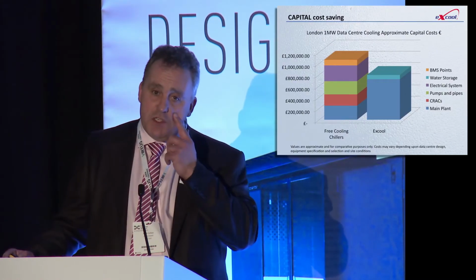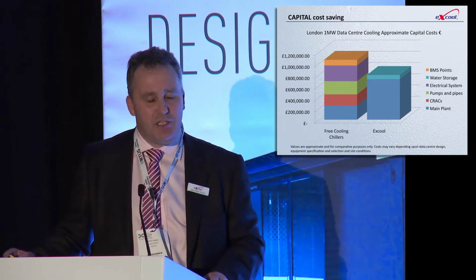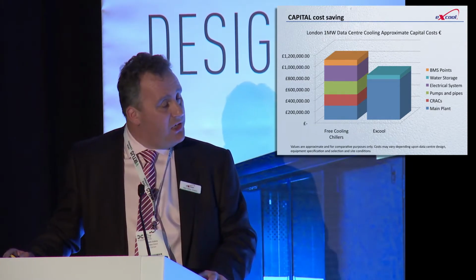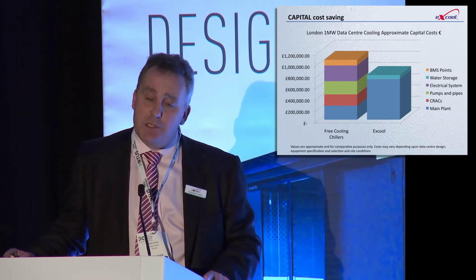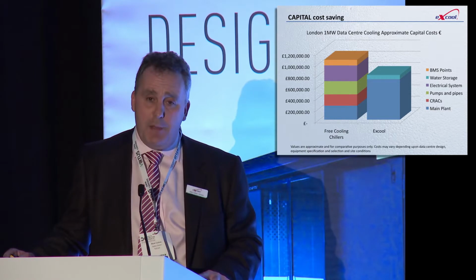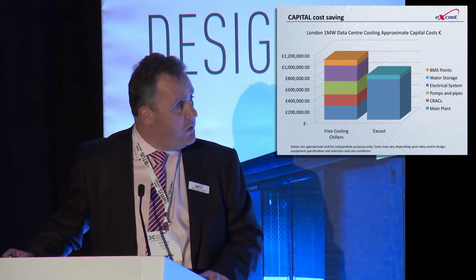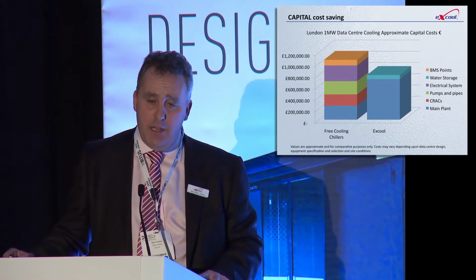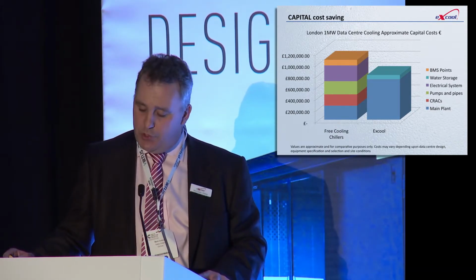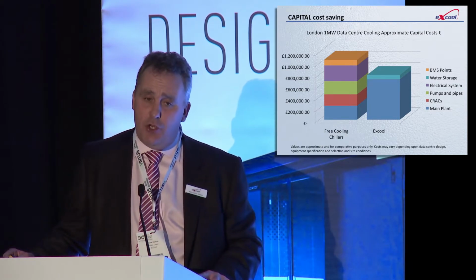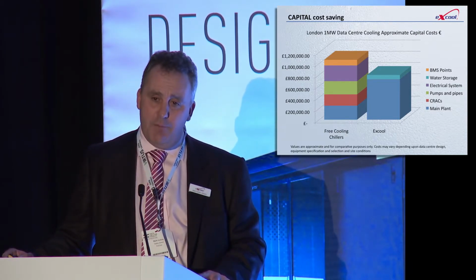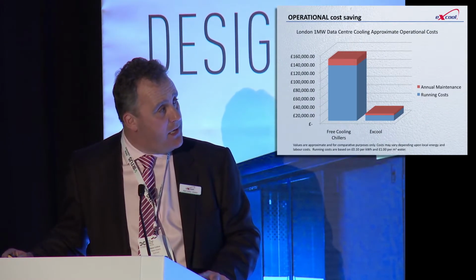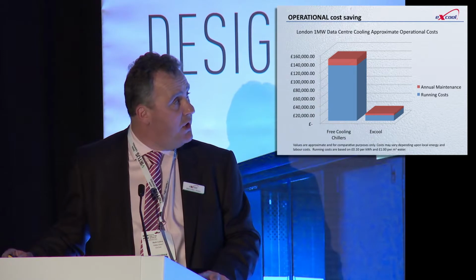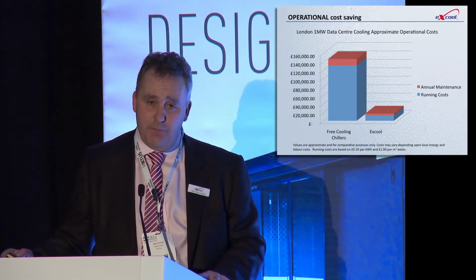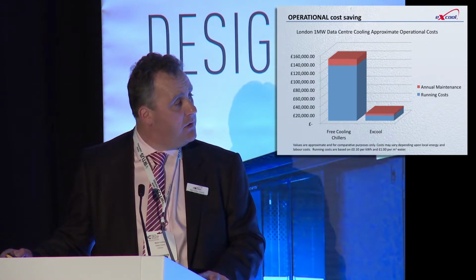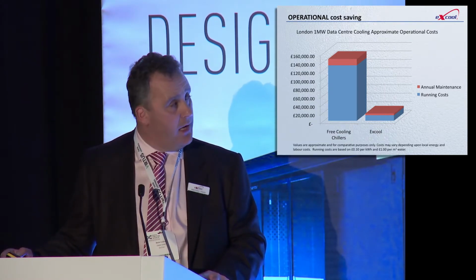So in terms of capital cost, I did begin this by saying that it's actually lower cost in the first place, lower energy and higher resilience. This demonstrates those costs, and these are fairly accurate based on feedback we've had from clients that have traditionally used chilled water. What we find is that the cost of the Excool unit and the water storage that is required for the Excool unit matches the cost of the basic mechanical cooling infrastructure. But there are significant savings to be made on the electrical infrastructure and the water storage, which is represented by this graph that I've got up on the screen now. It's a typical 1 megawatt data centre, N+1 in London.